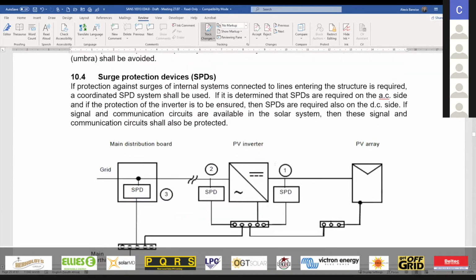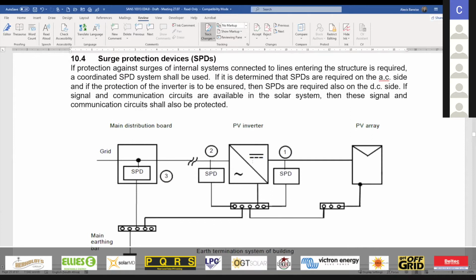And here you can see the drawing again. So from the DC side, there will be a DC SPD. On the AC side of the inverter, an AC SPD. If that length of cabling is long enough, so that's where the risk assessment comes in, then we would also put an SPD at the grid connection, because we're also trying to stop any of the Eskom switching surges, switching transients, from affecting the inverter from the AC side. So in most cases, you only have one, either number 2 or 3. On longer installations where the grid connection and the inverters are far apart, you would have both of those.